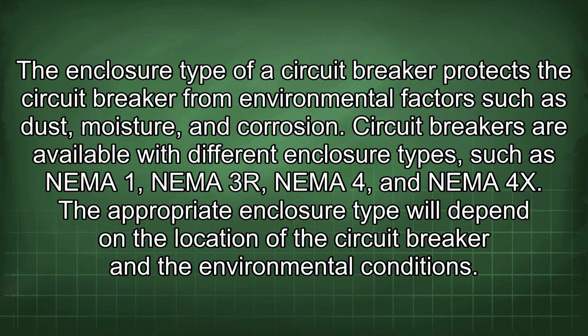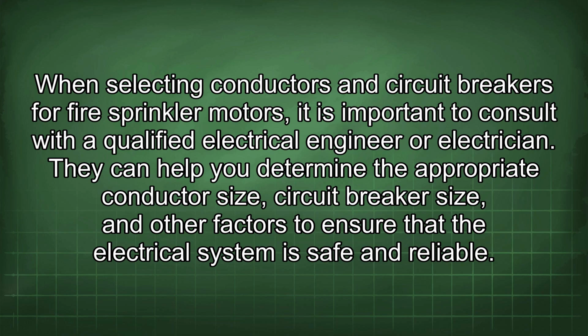The enclosure type of a circuit breaker protects the circuit breaker from environmental factors such as dust, moisture, and corrosion. Circuit breakers are available with different enclosure types, such as NEMA 1, NEMA 3R, NEMA 4, and NEMA 4X. The appropriate enclosure type will depend on the location of the circuit breaker and the environmental conditions. When selecting conductors and circuit breakers for fire sprinkler motors, it is important to consult with a qualified electrical engineer or electrician. They can help you determine the appropriate conductor size, circuit breaker size, and other factors to ensure that the electrical system is safe and reliable.